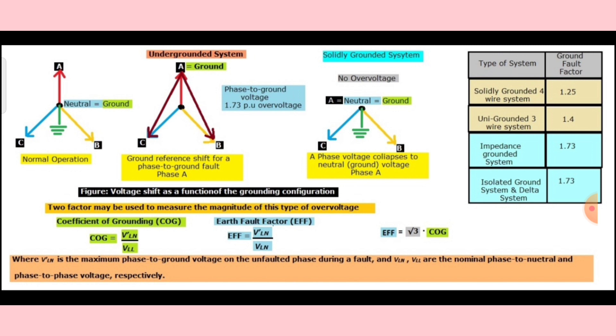That means if the maximum voltage that occurs in your system is VLN during the fault on the unfaulted phase, and you divide it by the rated voltage of your system, that gives you the coefficient of grounding.